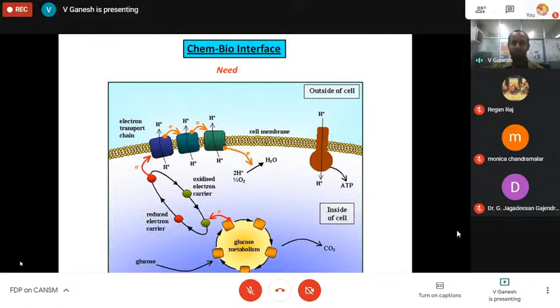That instrument is a typical example of a device developed based on a multidisciplinary approach. So that's why understanding the chem-bio interface becomes very, very critical. Now, let me tell you, in a minute or two, the classical book-based definition of what a sensor is all about. A sensor is nothing but a device which converts either a physical or chemical parameter into a measurable electrical signal. In general, it comprises a sensing element, that is nothing but your enzyme, the glucometer I talked about a while ago, and a transducer, which is nothing but your electronic interface, which picks up the changes occurring due to the enzymatic reaction, and the connected electronics will give you an electrical output signal.